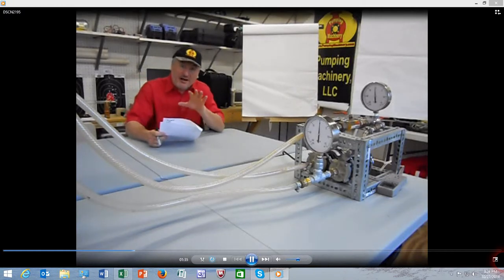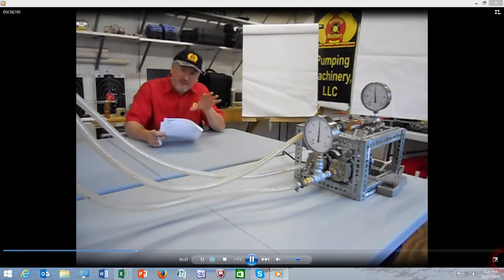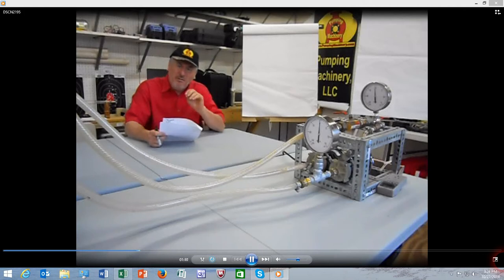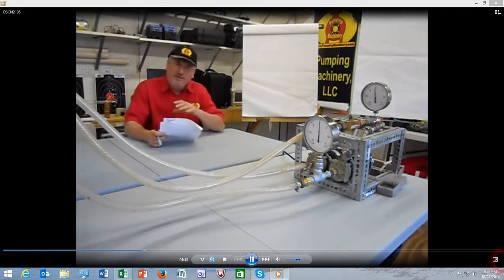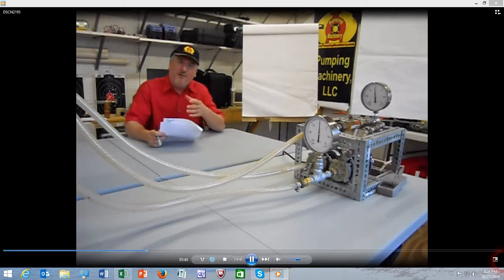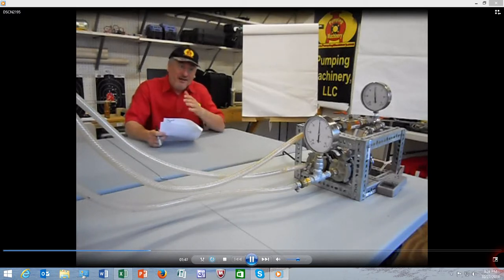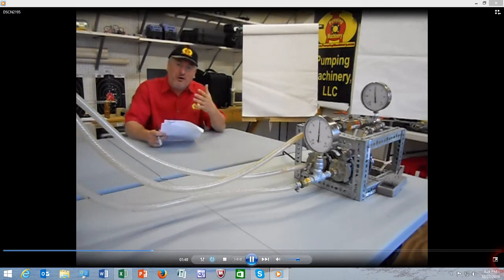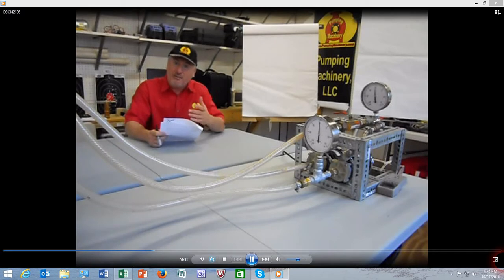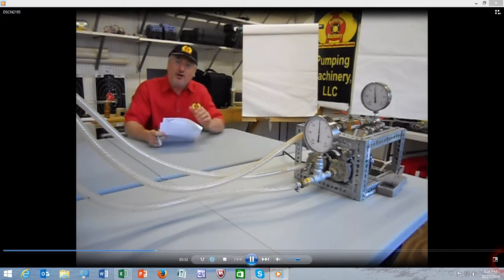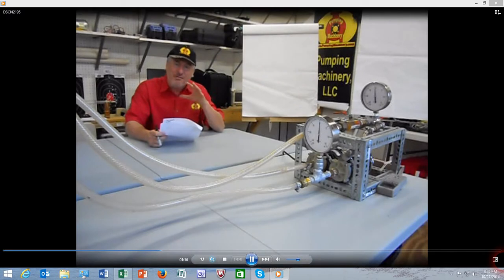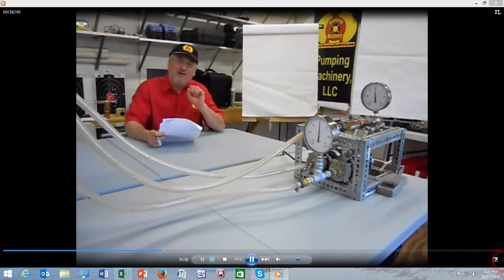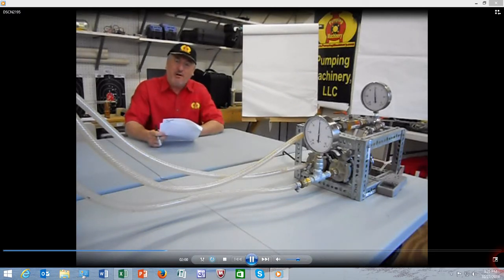In this formula, RPM, the speed is involved. But more importantly, it's the flow and the pressure, flow and head, that makes the shape of the pump, the type of the pump actually. Centrifugal pumps, multi-stage pumps like boiler feed pumps or vertical turbine pumps, the shape of the impeller determines the type of the pump. That is primarily what specific speed of the pump relates to.